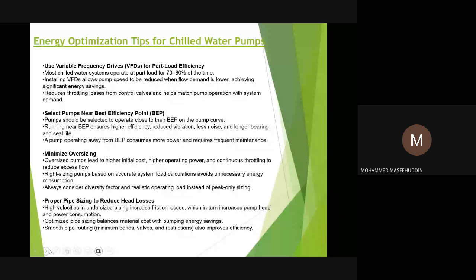For every pump, there will be one best efficiency point, like say 80% or 85%, 82% will be the best efficiency. So whatever pump we select based on our duty conditions, the selection should be very near to the best efficiency point. So that way we can also optimize the pump efficiency. Minimum oversizing, as we discussed in our last slide as well, the oversizing should be very minimal. And of course, the proper pipe sizing to reduce the head losses. So all these points will actually help in optimizing the chill water pumps within the segment.